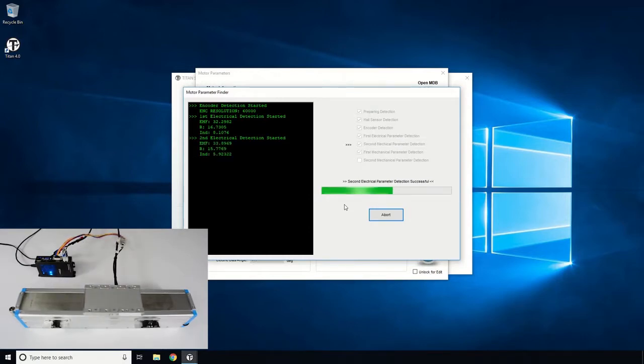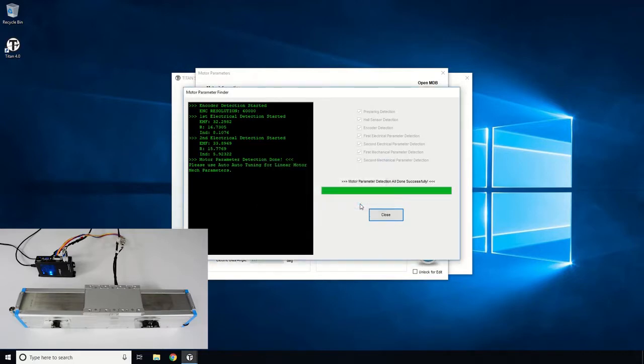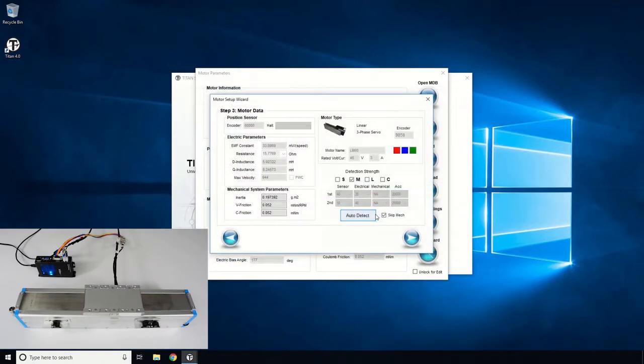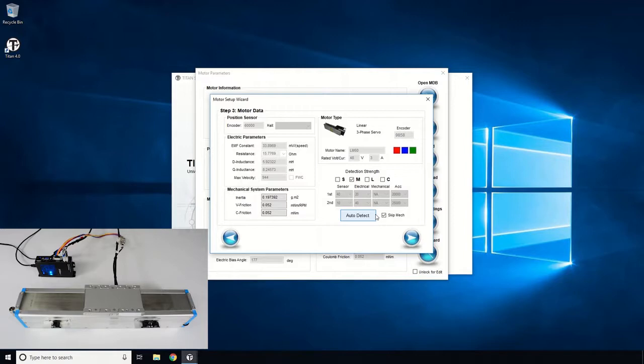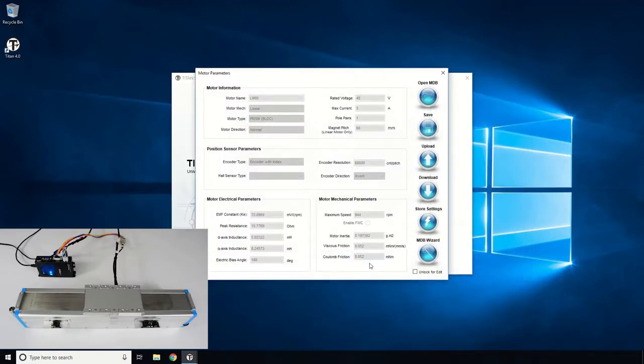After successful detection, the motor constant, inductance, and resistance values should be determined. Note that the linear motor mechanical parameters detection will not be done here, but later in the mechanical tuning page. Once the detection is successfully done, go to the next screen and save the motor parameters to a motor database file, so that the database can be used again later.